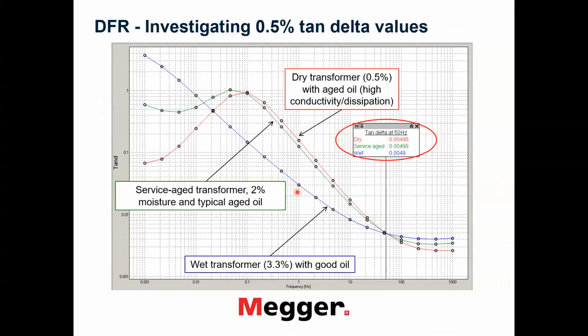So since we have two materials involved in a transformer, we could have a wet transformer with good oil, we could have a dry transformer with bad oil, and we could have just a regular transformer. And the issue here is that at power frequency, all of them would perhaps show the same value of the tangent delta, which is not high, but close to values where you should start to pay attention.